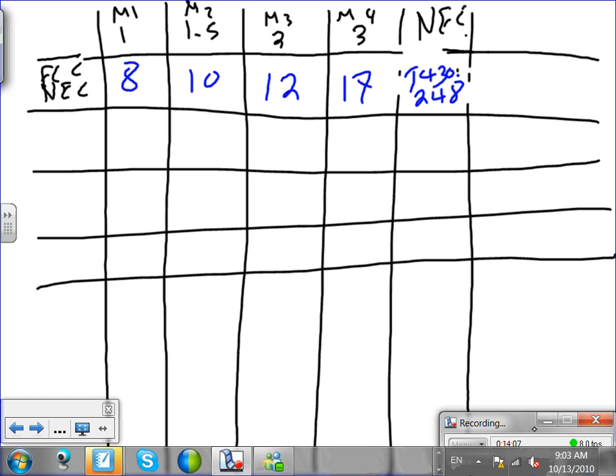Okay, so number one. Now let's go ahead and calculate that. Number one, disconnect for motor number one. Here's the calculation that we're going to do for the disconnect. The article that talks about disconnects for motors is article 430.110. If you go there, it will tell you to size the disconnect. You have to multiply the full load current from the NEC by 115%. To size a disconnect, you need to take the full load current and multiply it by 1.15.